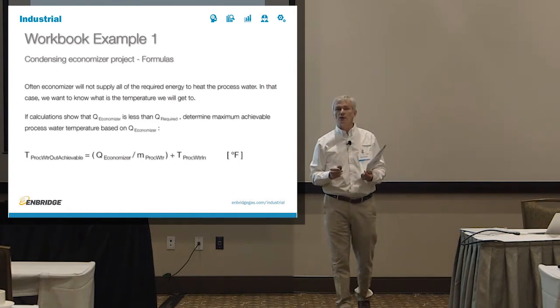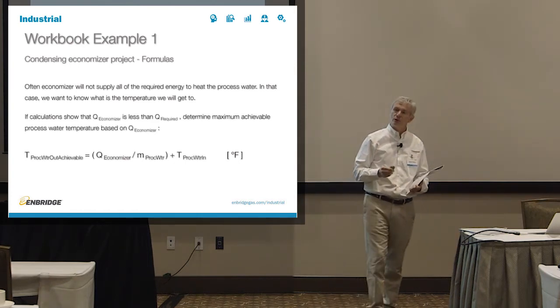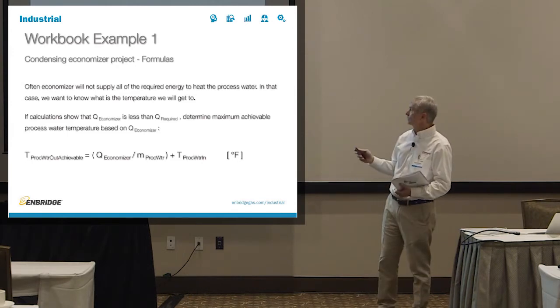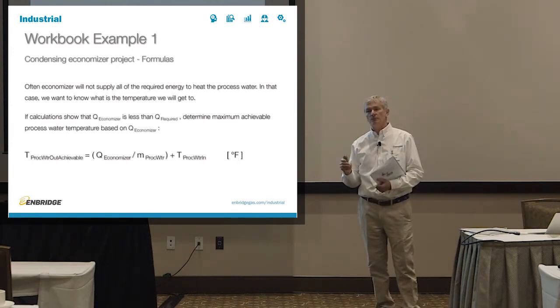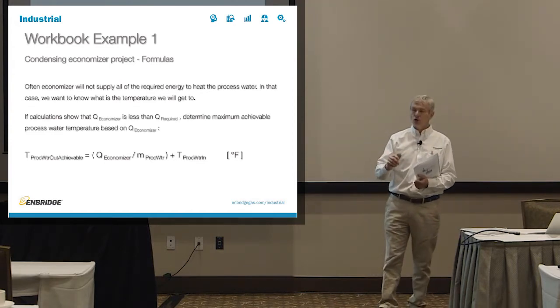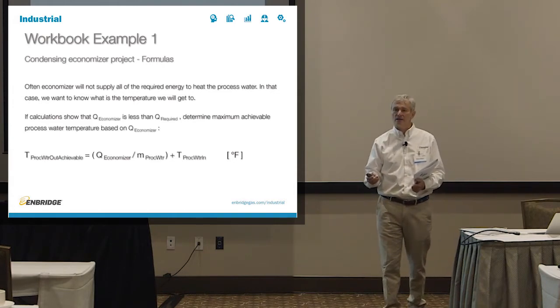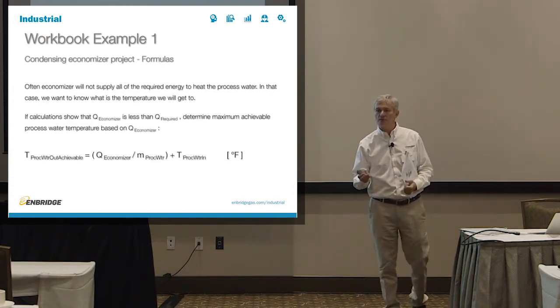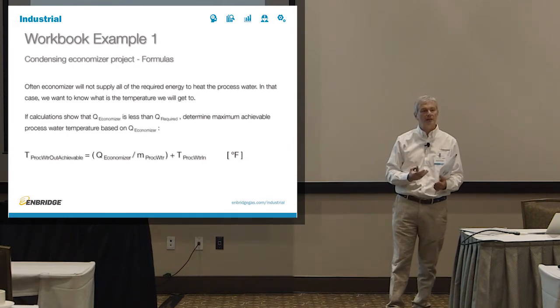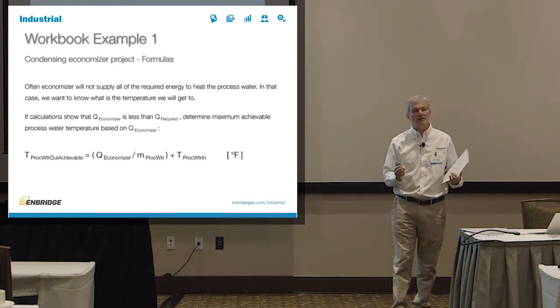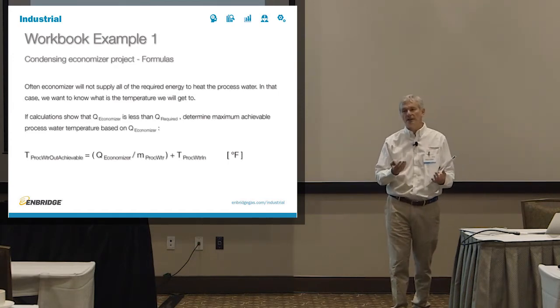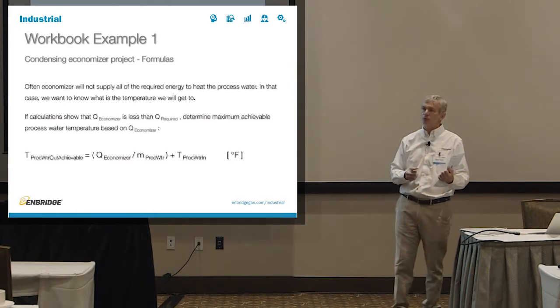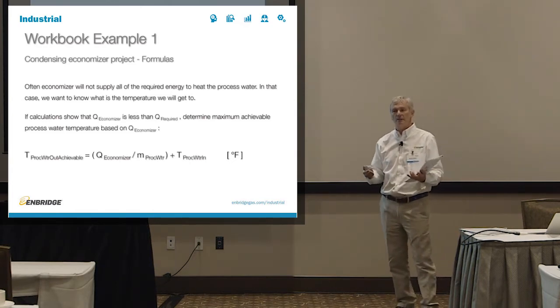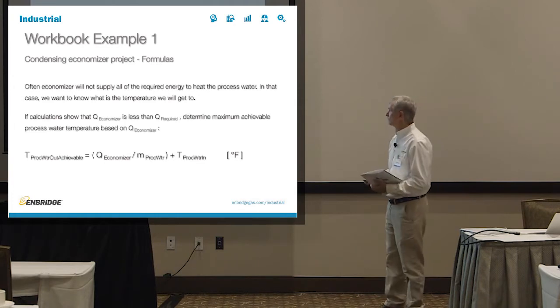And once we figure out how much heat we recover out of the condensing economizer, we'll do one additional step. We will find out, can the condensing economizer actually supply all of the heat to get us to 170 degrees F? And if not, what is the end temperature that it can supply? It's very important to know, because if you have a requirement of 170 degrees F at the exit and you can't reach it, you would want to also size, let's say, a small heat exchanger or some other method to top up that heat from the condensing economizer. Then once you take everything into account, you see whether that's a good business case to pursue or not.